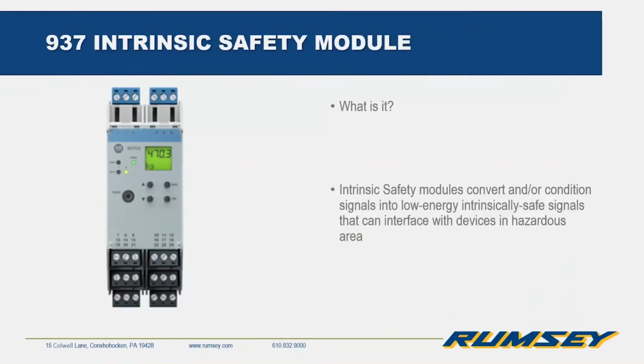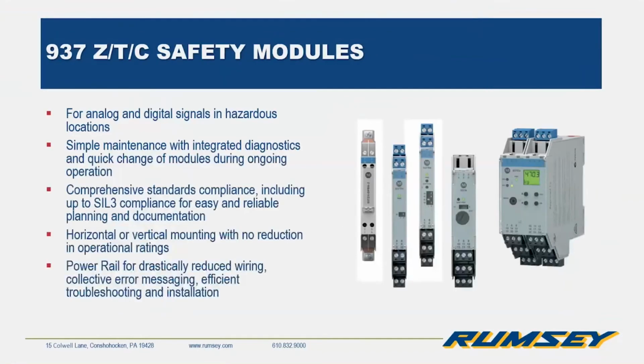So now we'll move on to intrinsic safety modules. Essentially, these are easy ways to interface with devices in hazardous locations. Kind of to take a step back, a device in a hazardous location needs three things. It needs air, oxygen, a flammable substance to cause an ignition, and then a spark or a source of ignition. And essentially what we're doing with these devices is we are taking out the ability to cause a spark. So essentially, an intrinsically safe circuit should not be capable of causing any kind of ignition during normal operations. And essentially we want to keep the energy to a minimum.